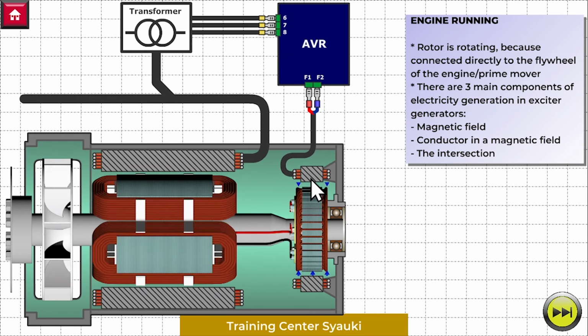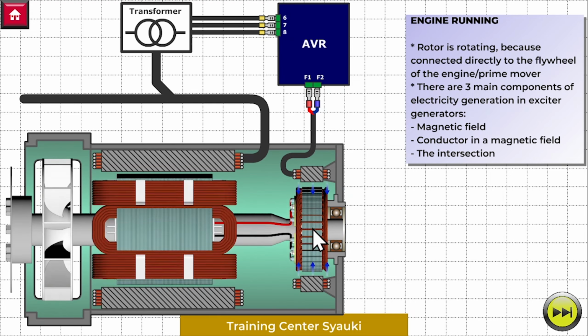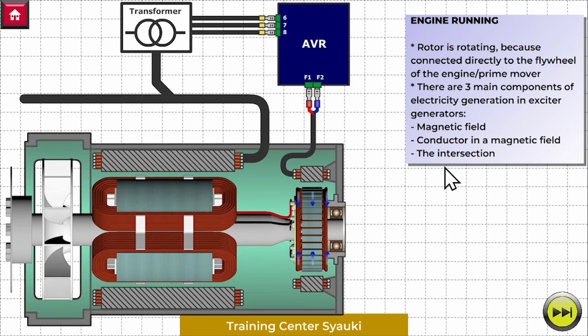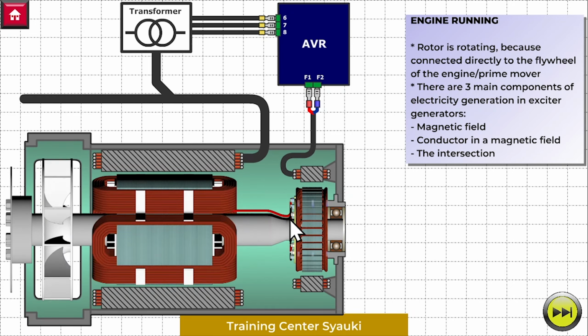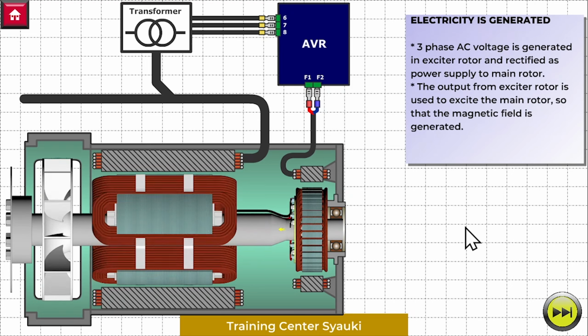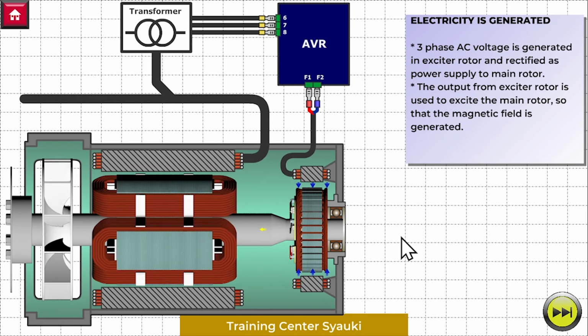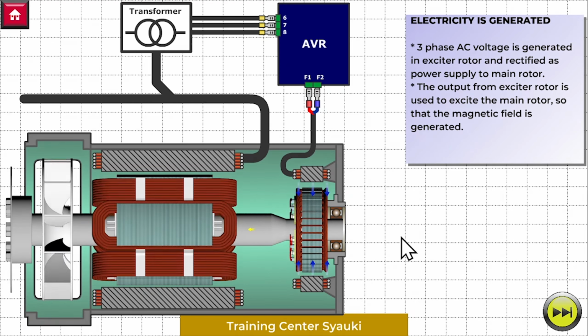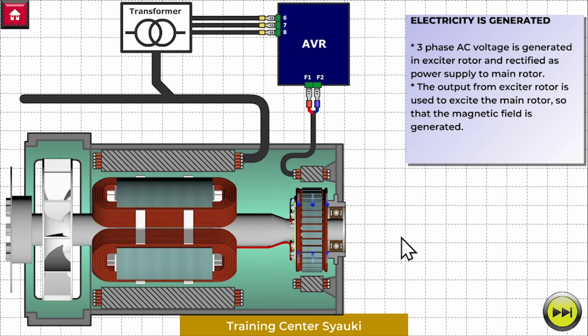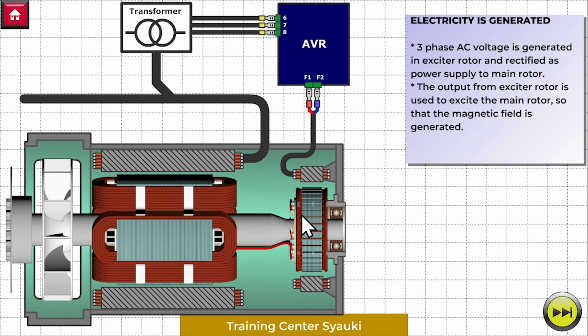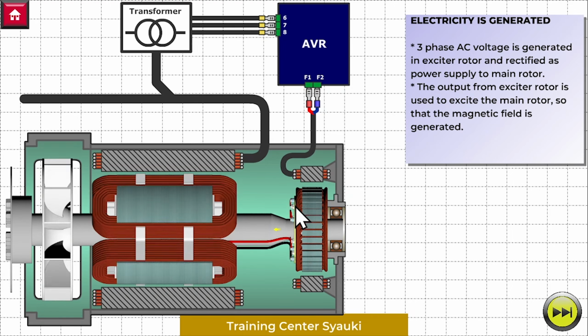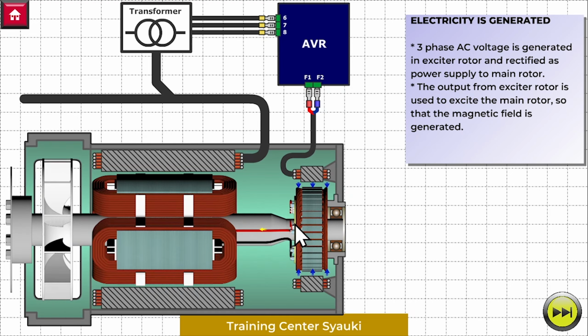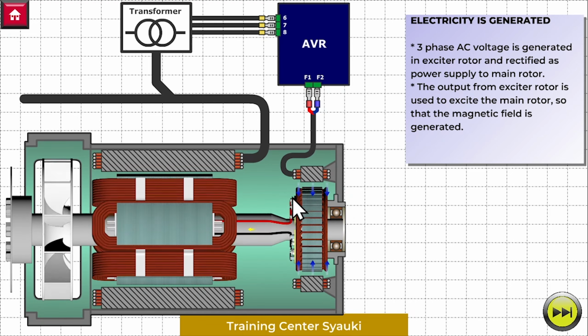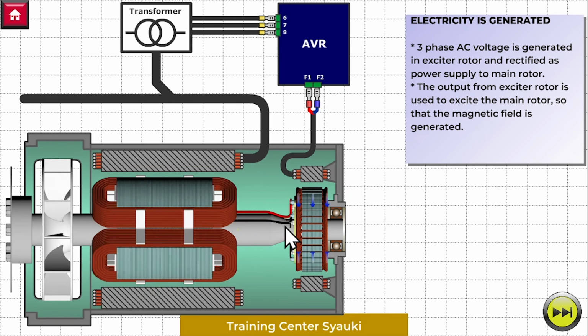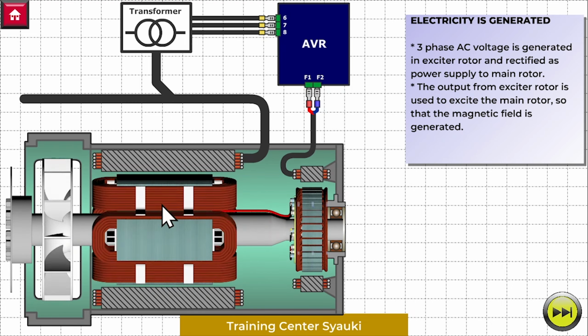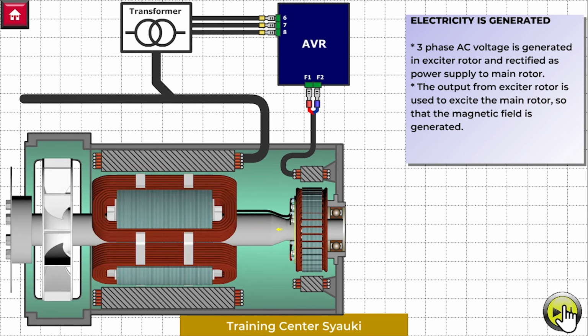So once this happens, the intersection is completed and the three main components come together. What happens next? Electricity is generated. Three-phase AC voltage is generated in the exciter rotor and rectified as a power supply to the main rotor. First, the output of the rotor is three-phase; then, because it must flow through the rotating rectifier, it converts from AC to DC. The output from the exciter rotor is used to excite the main rotor, generating the magnetic field.